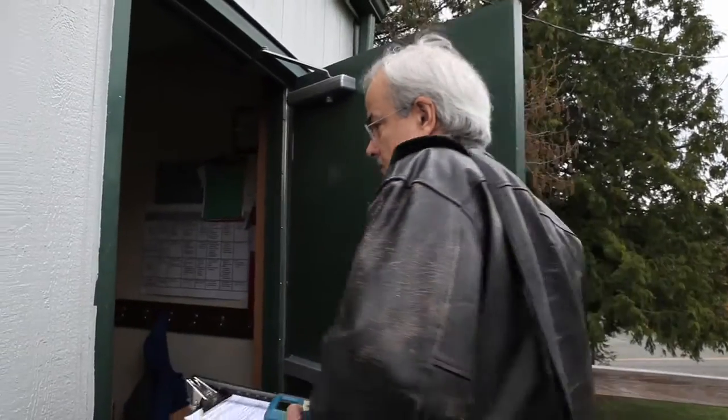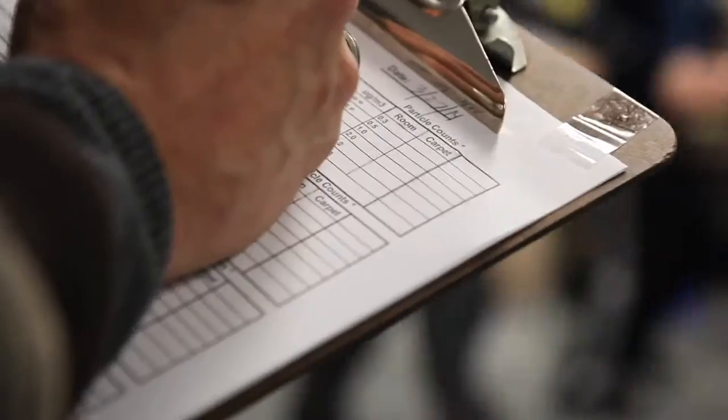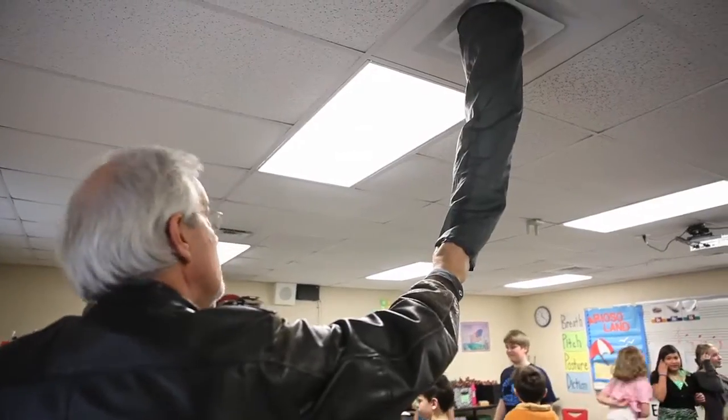Dave Blake is an indoor air quality specialist for the Northwest Clean Air Agency. He's tested air quality in more than 3,000 classrooms in Washington state. We have a lot of fancy equipment, but you don't really necessarily need it. You can walk into a classroom and right away, if you can smell the humanity and taste the humidity, you know you've got a ventilation issue.